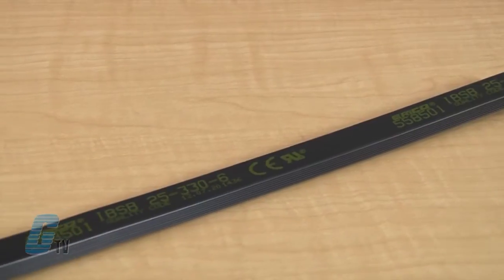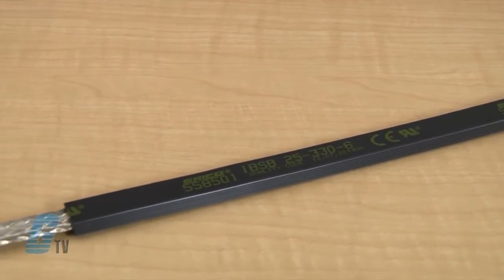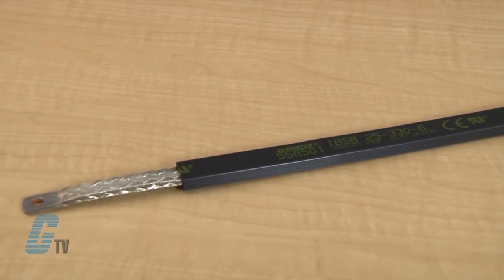These insulated braided conductors can directly connect on the front access terminals of breakers from 80 to 350 amp circuit breakers without the need for additional accessories such as angular connectors, spreaders, ring terminal connectors, or extenders.